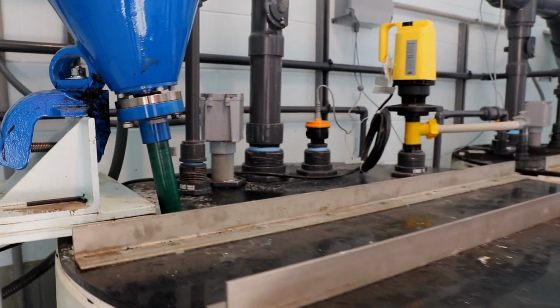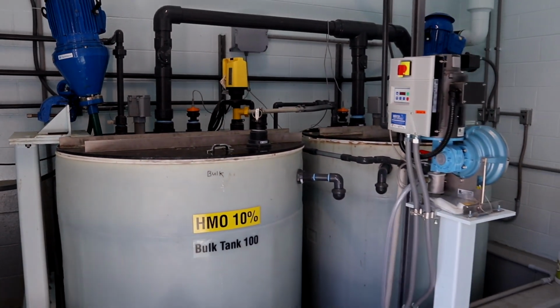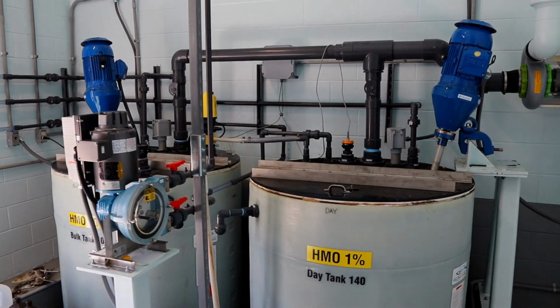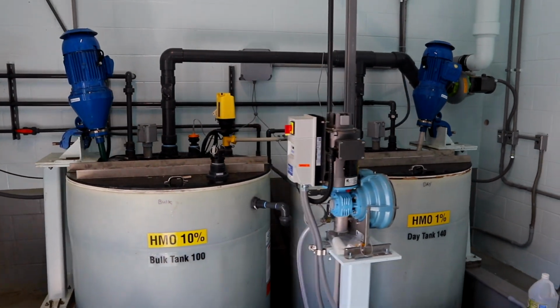Right. Can you tell us a little bit about the mitigation of radium with the 2 products? Yeah. I would assume we're in compliance at this point. I think we started around 2008 or 9. Is that correct? Yeah, we're in full compliance. In years prior to 2008, the MCL was changed significantly. So Rockford was tasked with coming into compliance with the new 5 picocurie per liter rule.